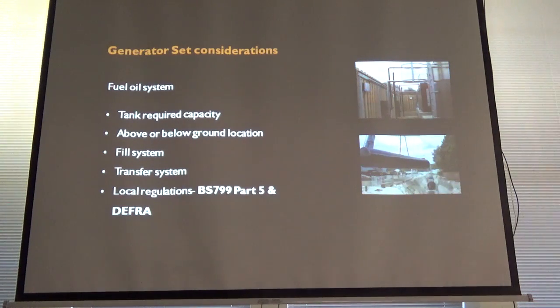And it's coverage of duty of care as well that is always one of the key things. Asking the right questions, getting the right answers, saying and recommending, and obviously then tying them in with the legislation, the DEFRA requirements, the transfer systems, the capacities required. Often sets on the roof, certainly in London, they'll have a dump requirement, go back to the bulk tank. So the fill on a bulk tank may be this size, say this is 1,000 litres. The fill requirement on that bulk tank, of course, is going to be its capacity minus 1,000. That's its 100% fill. Because otherwise, if you get a dump situation where you've got a fire in that unit, you'll have it spilling everywhere.